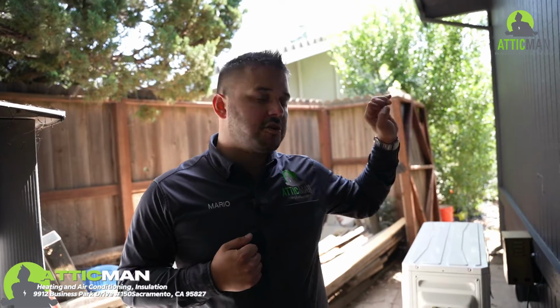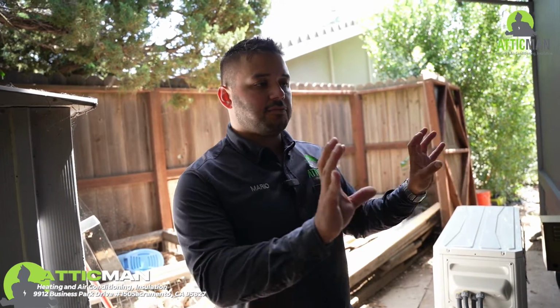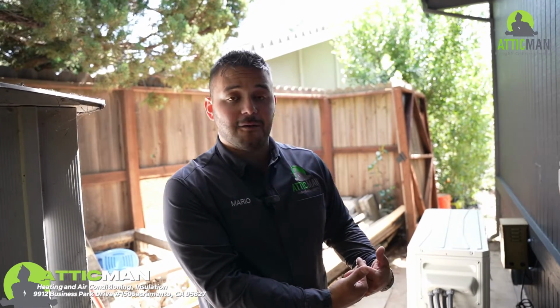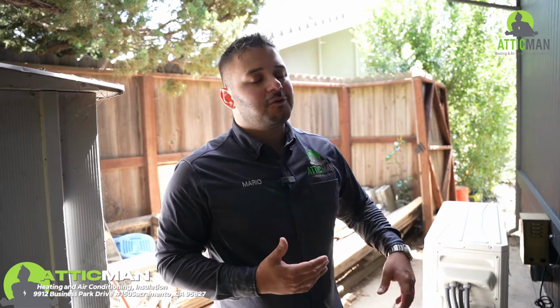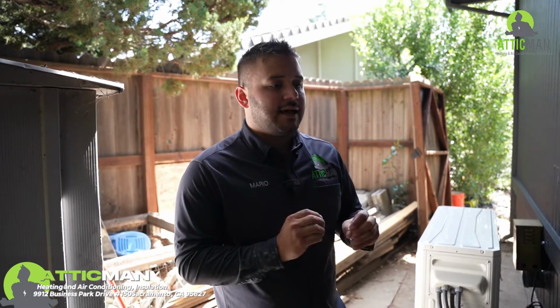This is another thing I see with salesmen and contractors, is they might undersize the outdoor unit and the homeowner has no idea, and it's not an issue until they have to run all the heads at once, and now all of a sudden this unit that you're used to cooling is not cooling as much, right? Because if you undersize the outdoor unit, the system will still operate, right? Let's say, for example, this only had 24,000 BTUs, right? And I have 3 9K heads, I turn them all on. All 3 of them are going to turn on. They are going to produce cool or hot air. However, they're not going to be running at full capacity, right? Because we have 3 9K heads, it's calling for 27,000 BTUs worth of power. If the outdoor unit's sized for 24, then the outdoor unit can only handle 24, right? So if the outdoor unit's running all 3, that means it's going to split the difference between all of them, right? You're gonna actually have each head running at 8,000 BTUs, 8, 16, 24, versus the full 9,000 BTUs, because the outdoor unit simply cannot handle the demand.